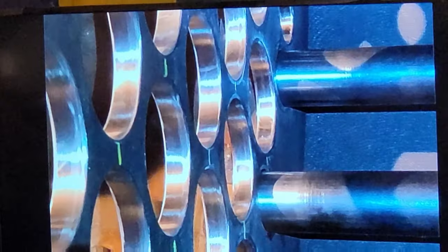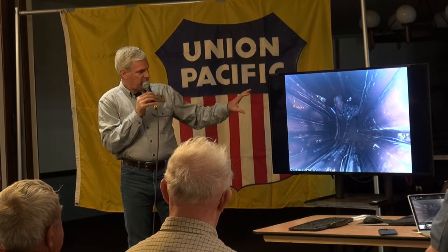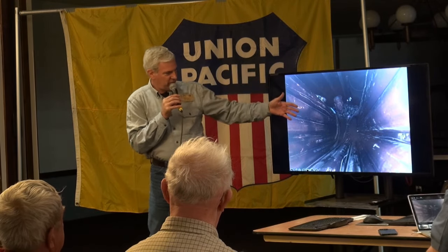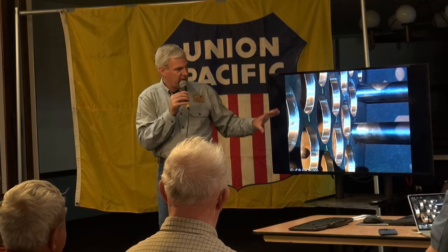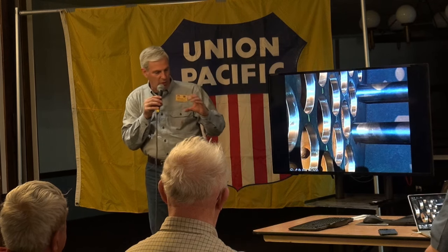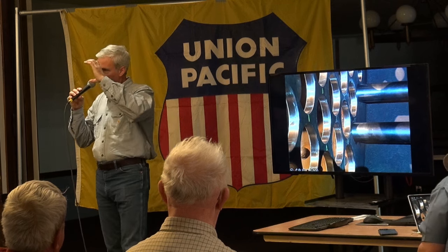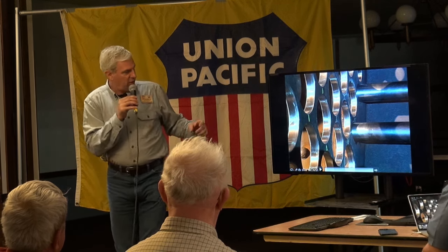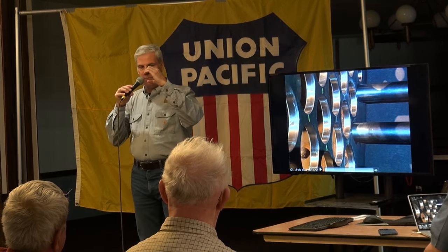Well, here we are back in the front tube sheet again. This is how we connect all that stuff together. But look at the beautiful, shiny surfaces of the metal. And that's how you put that stuff together. So you clean up the tube, you clean up the hole. And the hole has to be a specific dimension. It can't be too big, can't be too small. And you have a special device called a tube roller, and that physically expands the metal of that tube.